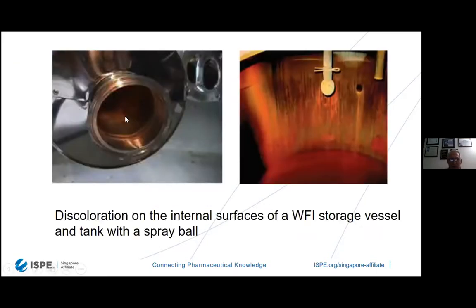Here are two different vessels. The one on the left is a WFI vessel. The one on the right is also a storage vessel with a spray ball. And you can see the dark rouge over here on the right-hand side. This rouge has been there for a while. It's very extensive and it should be removed. It's not only the discoloration, but the point is that it could cause corrosion over time to the vessel. Also, when you do derouging passivation, it will remove some of the metal from the metal layers, which means that the thickness of the metal will degrade over time.